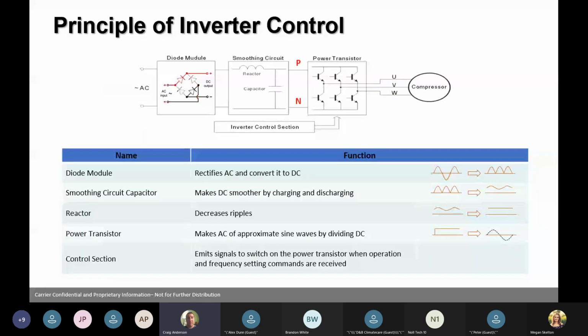So here's another picture. AC voltage is coming in, we're smoothing it all out and sending it to the transistors, and then we're going to the compressor. Notice how the ripples have changed. We're getting big ripples, and then we're smoothing the curve to DC voltage to make it cleaner, because AC voltage is usually dirty, especially if we're working in commercial properties or old farmhouses where we have a lot of poles going to the house.